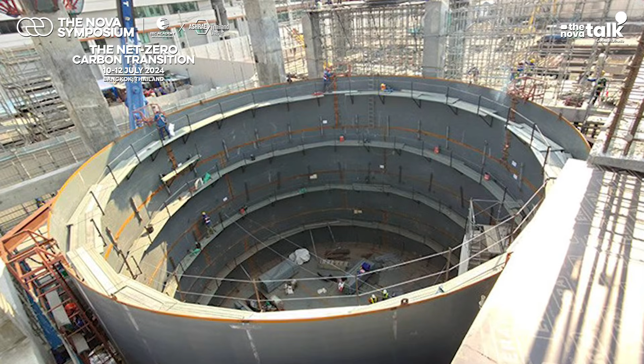So there are multiple ways to decide how we would go about thermal storage. It depends if in Thailand, let's say, or some regions, you might have demand costs for electricity or not. So if there are no demand costs, for example, in the UAE and GCC, we don't have demand costs. So in that case, we're trying to load level the chillers and run the chillers at high load factor and high capacity. And in that case, we are always making sure the chillers are running at their best efficiency point.